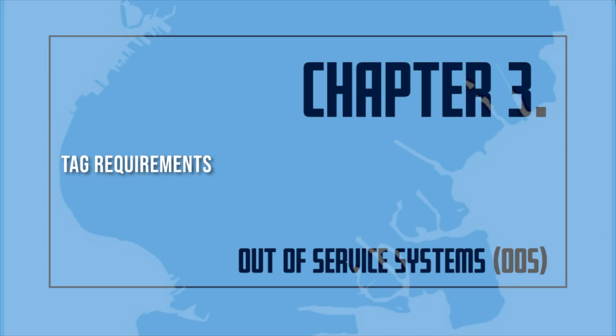Tag requirements. A tag shall be used to indicate that a system or portion is out of service. A master fire suppression piping contractor, Class A or B, or master licensed plumber, as restricted, shall be required to post tags at the main control valve and at any closed sectional valves serving areas affected. The tag shall indicate the area affected, a brief description of the condition, the occupancy classification, the certificate of fitness number, and the estimated time until the system becomes operational. Drain test results shall be posted on the tag, indicating both the static and flow pressures before and after the system was placed in an out-of-service condition. If no impairment is found in the entire system, green tags will be placed on the main control valve.